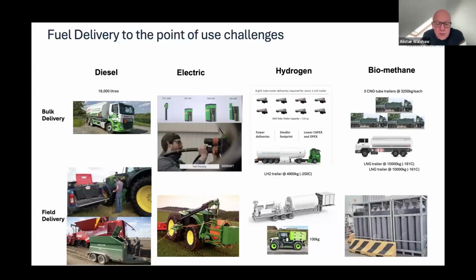If we look at electric vehicles, as they encroach on larger power-hungry activities, what is considered an on-highway fast charger of 130 kilowatt capacity will need a good three-phase supply, which is a rarity for many rural farms. And even then, the tractor will be on charge for roughly the same time as it is working, one hour on, one hour off. I will gloss over the John Deere 1 megawatt machine, which would draw the same daily requirement as approximately 200 houses, so a small village per tractor.